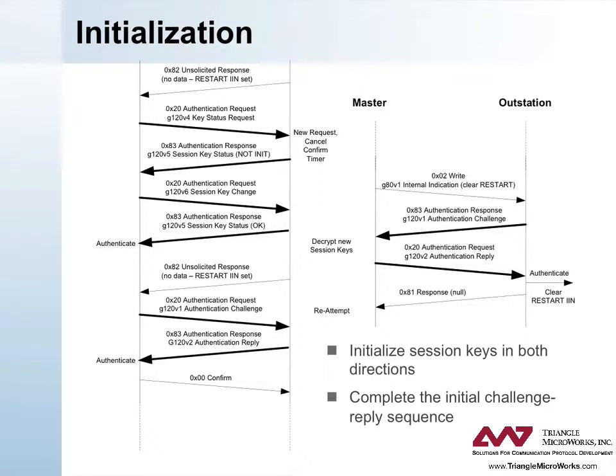This diagram shows how a master would typically initialize secure communications with an outstation. The outstation generates an unsolicited response to notify the master that it has restarted according to the normal rules of DNP3 unsolicited responses. Rather than confirm the unsolicited response, the master first initializes the session keys. By the rules of unsolicited responses, the outstation is required to abandon the original unsolicited response in favor of the session key transaction. When the outstation reattempts the restart unsolicited response, the master challenges and authenticates it before supplying a confirmation. The outstation does not require authentication of the master's confirm. However, the outstation does challenge the write operation to clear the restart IIN. Following this sequence, both sides are permitted to use aggressive mode because a complete challenge-reply sequence has taken place in both directions.